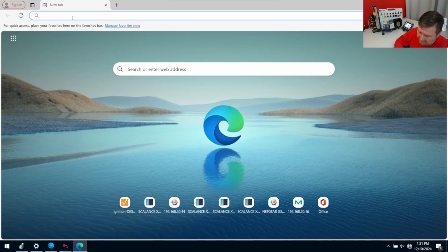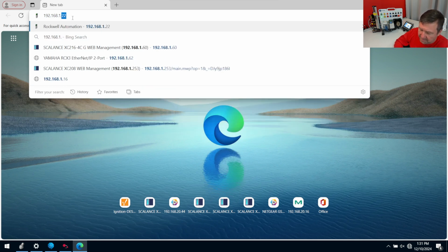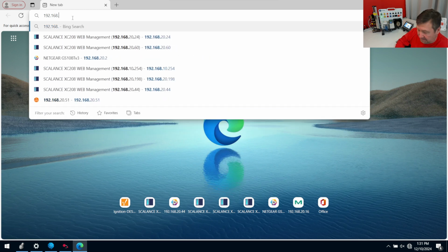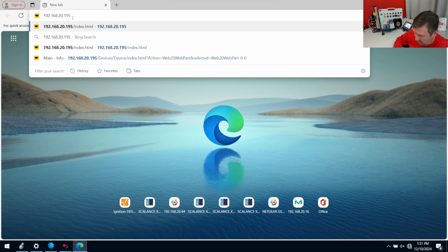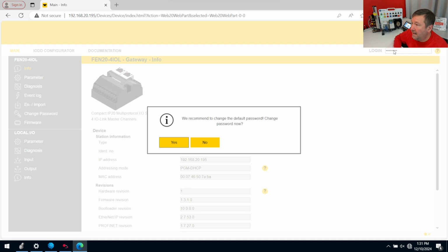Now let's look at the web interface and see what we can learn in it. Now your default IP address is 192.168.1.15. Now for the videos, I actually have this one assigned to 20.195. Don't enter this number. It's just so I can show you what you'll see in there. And then in the top right, we're going to see a login. And the default password is password, P-A-S-S-W-O-R-D, all lowercase. And it's going to ask you to change the password, and you want to click yes and go ahead and change it.